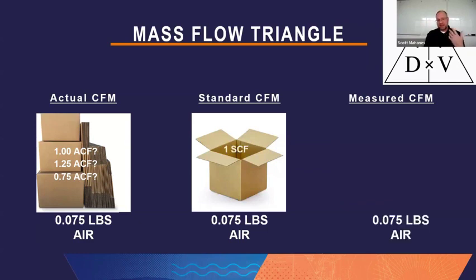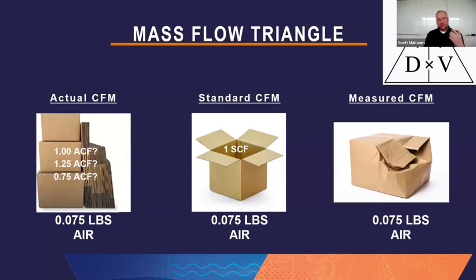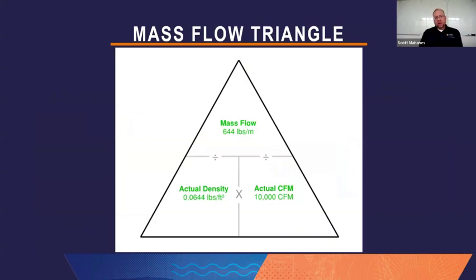Measured CFM, again, comes in damaged if it's not corrected for correctly. And oftentimes, I liken it to ordering from wish.com or temu.com. It kind of becomes like a questionable product. So here's that triangle, and I'm going to share an example with you on a 10,000 CFM RTU, a constant volume RTU.